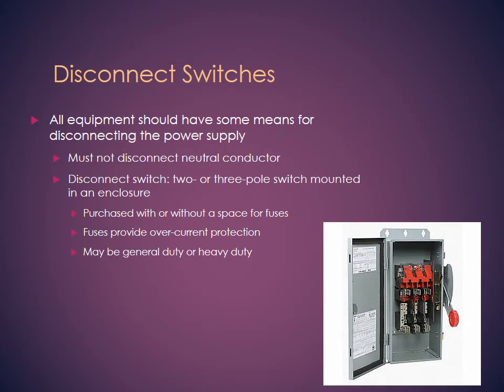Disconnect switches. Every piece of equipment needs to have a disconnect switch, especially for heavy loads like an air conditioner or a boiler, and usually we connect through the hot line. So if we have 3 disconnects here, that means we have 3 hot lines. The disconnect switches should be on the hot line, not on the neutral. Some of them have fuses, some of them don't, depending on the load and the code. Fuses provide overload protection, similar to the breaker, which will trip. This one will just burn.